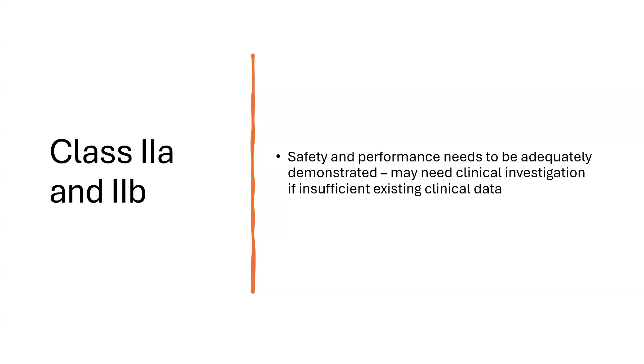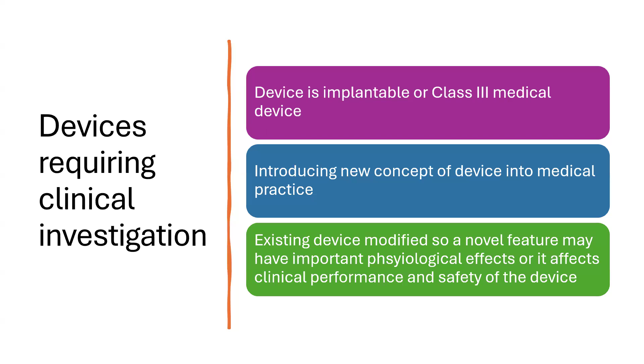Now coming to the next point, devices requiring clinical investigation. That is, the device is implantable or a class 3 medical device, introducing a new concept into medical device practice, or an existing device that is modified so that a novel feature may have an important physiological effect. So they are saying that class 3 medical devices may have some physiological effect. It needs to be qualified by clinical performance, and the safety of the device is the prime focus and needs to be ensured while using class 3 medical devices. Sorry guys, I keep saying drug instead of device.